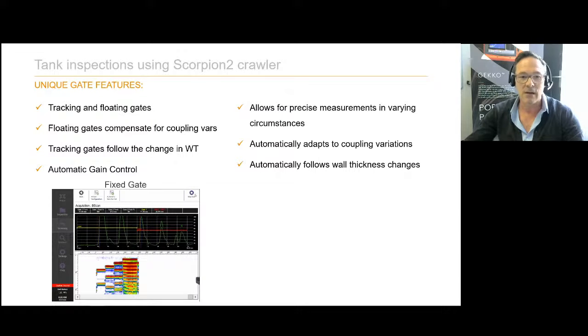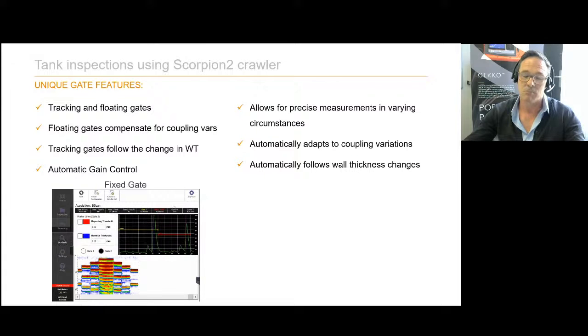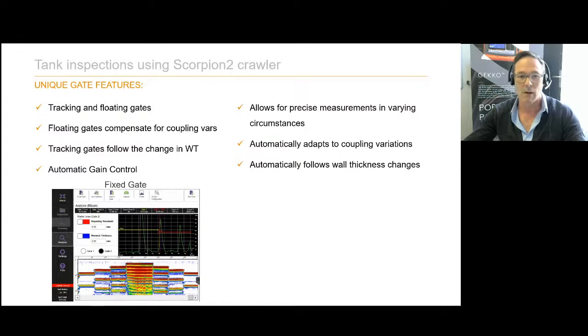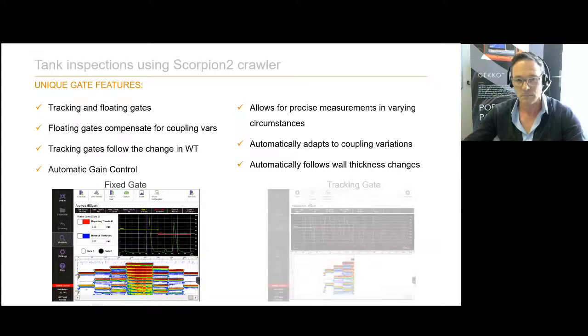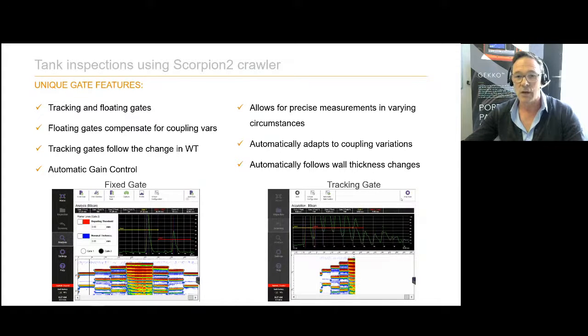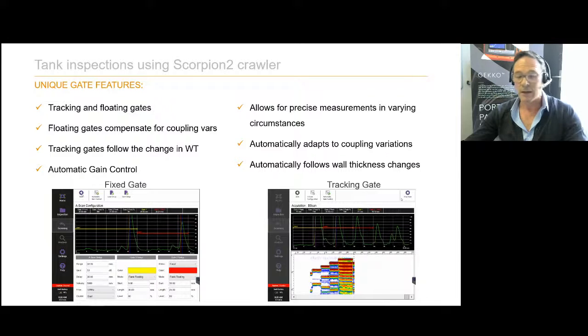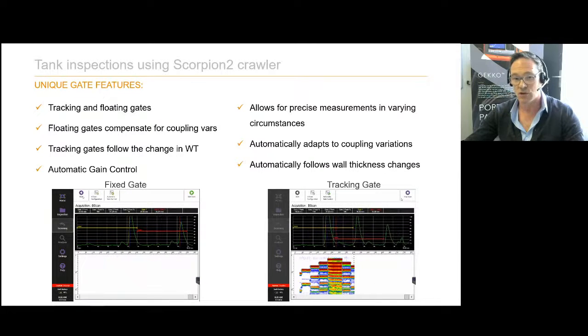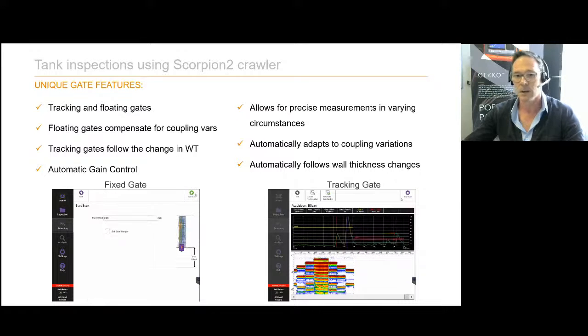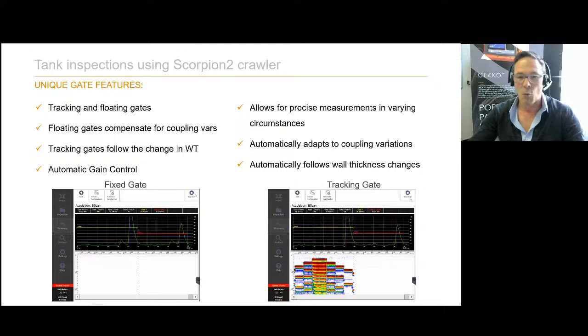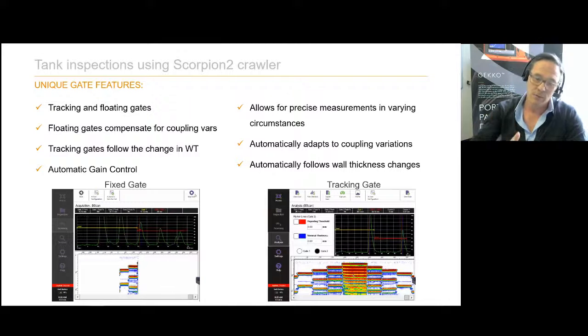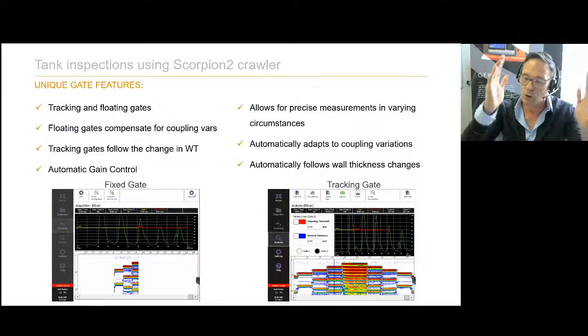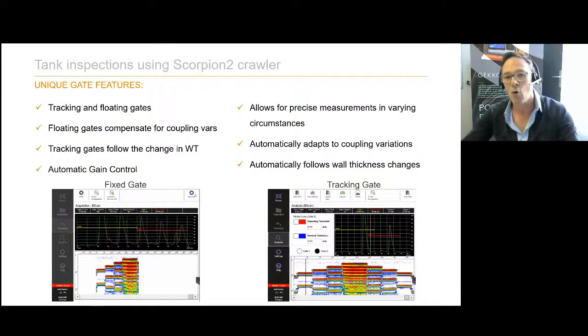So if we look at the fixed gate, for instance, you can see that the echo, the wall thickness is changing, the echoes are changing, but my gate is fixed, meaning that I don't have a correct reading on my second back wall echo, which will make it very hard to actually use that signal for interpretation. If we then have a look at the tracking gate, we can see that gate is automatically tracking the material thickness as it changes, and it will automatically adapt to whatever wall thickness it is currently measuring. We all know that tank shells on the bottom are quite thick, on the top they're quite thin, so this gate will actually follow the wall thickness.